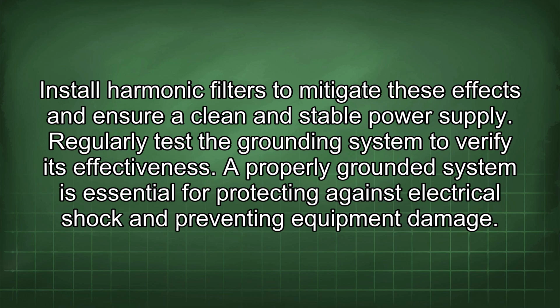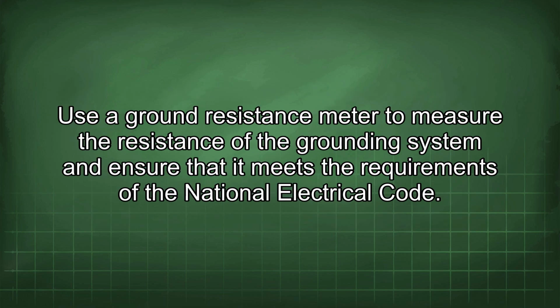Regularly test the grounding system to verify its effectiveness. A properly grounded system is essential for protecting against electrical shock and preventing equipment damage. Use a ground resistance meter to measure the resistance of the grounding system and ensure that it meets the requirements of the National Electrical Code.